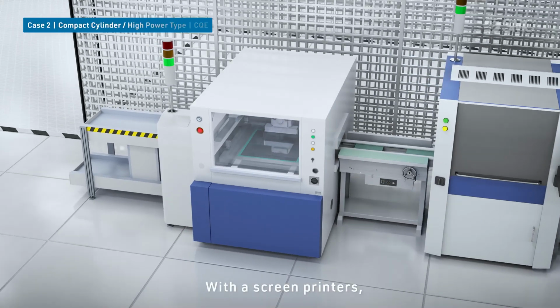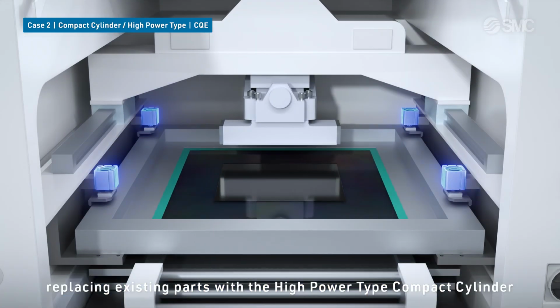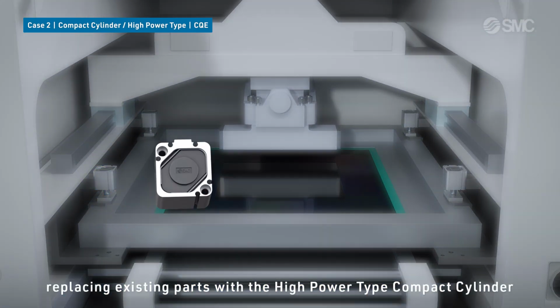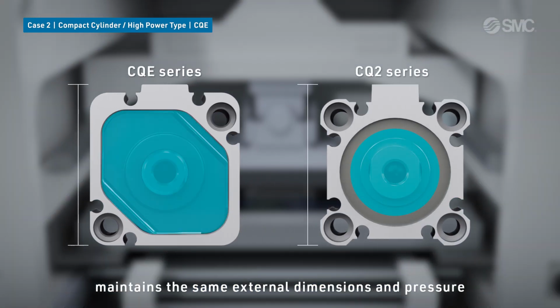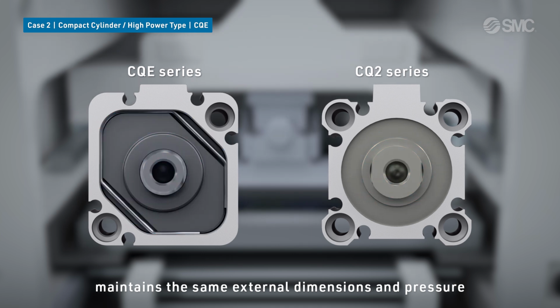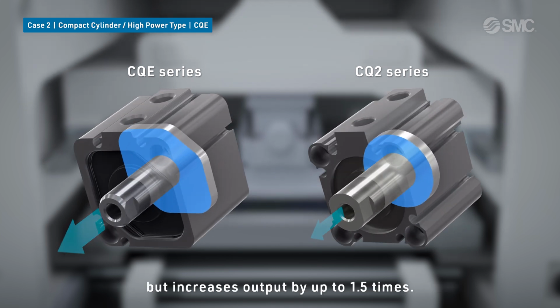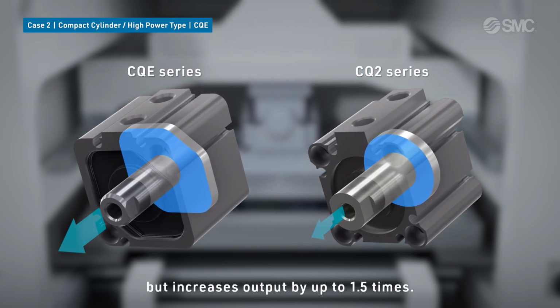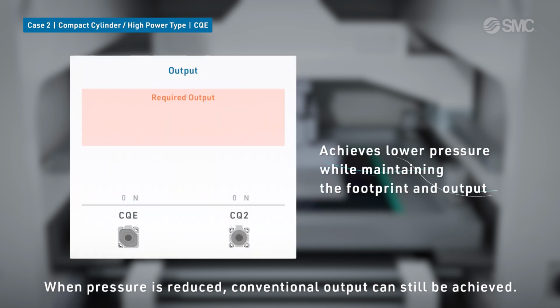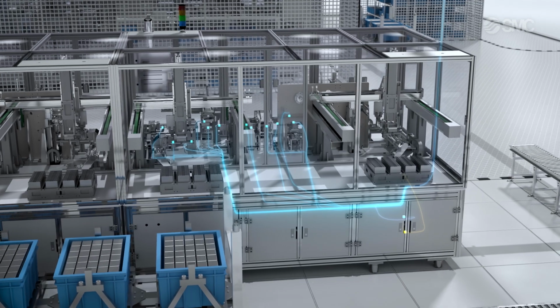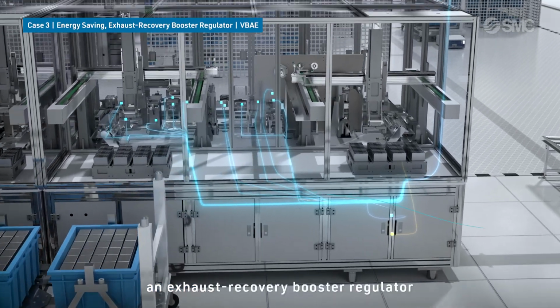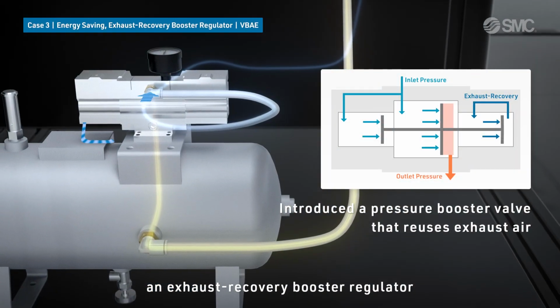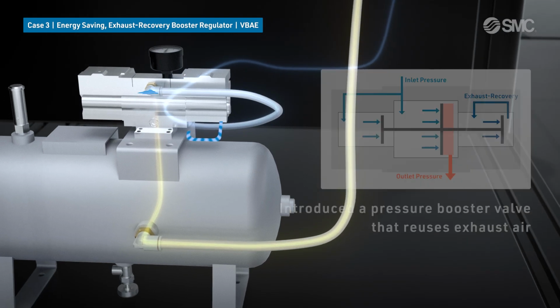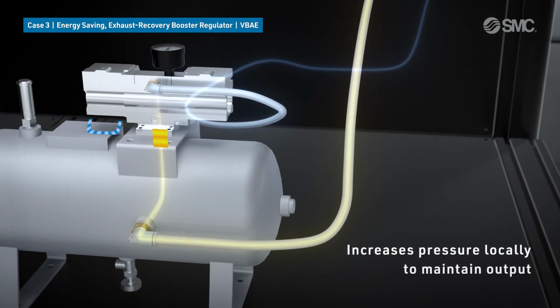With screen printers, replacing existing parts with a high-power type compact cylinder maintains the same external dimensions and pressure but increases output by up to 1.5 times. When pressure is reduced, conventional output can still be achieved. With an assembly unit, an exhaust recovery booster regulator can be introduced to locally boost pressure to maintain output.